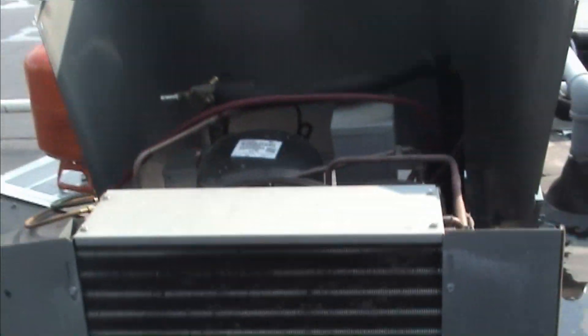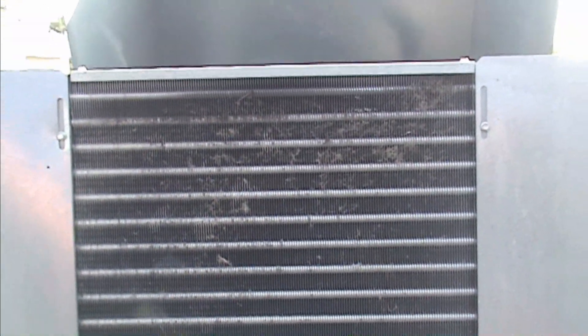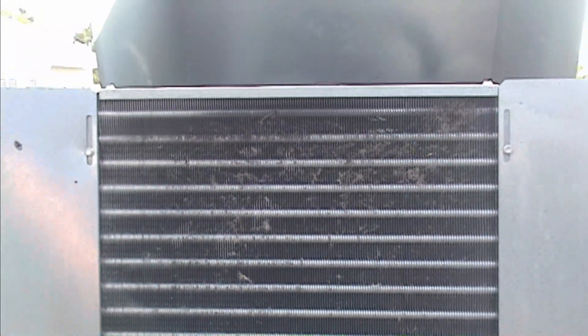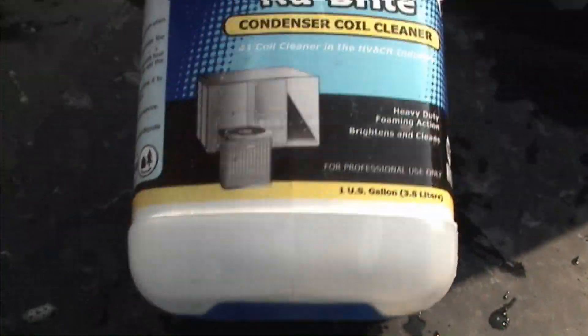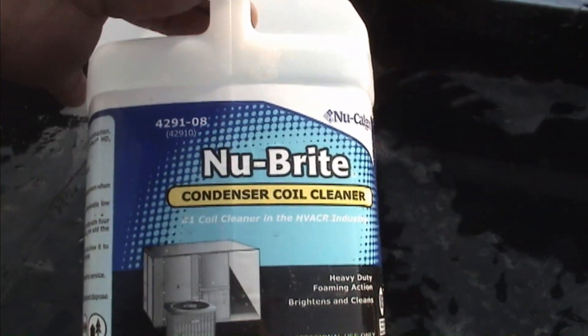Even though this doesn't look that dirty, I know that it's filthy because my head pressure is through the roof even though I have a leak. So we have to clean this. This is a very small coil, but the same thing would go for your air conditioning at your house, whether it be a split system or even a window unit. The cleaner we're going to use is the Nu-Brite Condenser Cleaner — the blue stuff, not the pink stuff. You can get this at any refrigeration supply house. One gallon is more than enough.